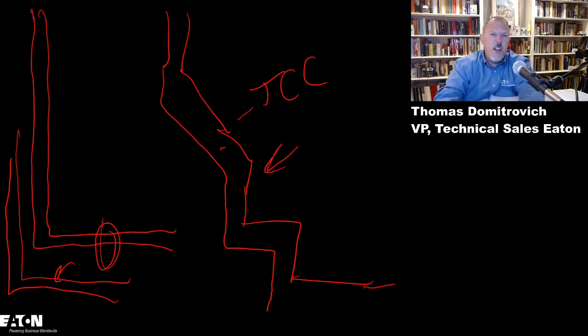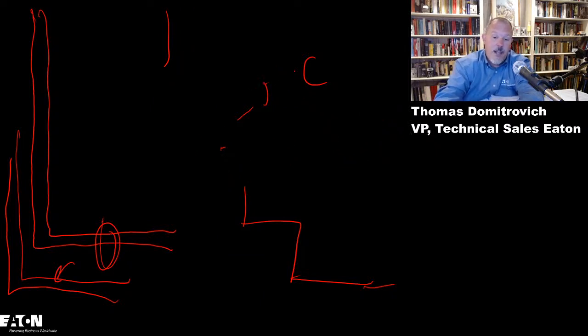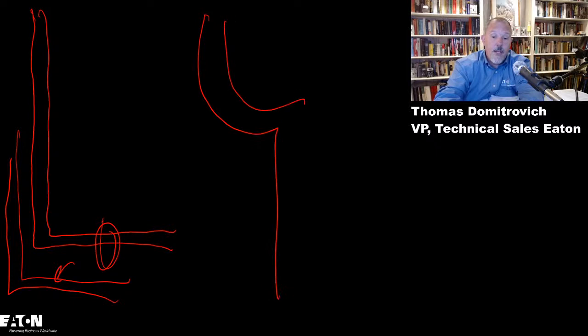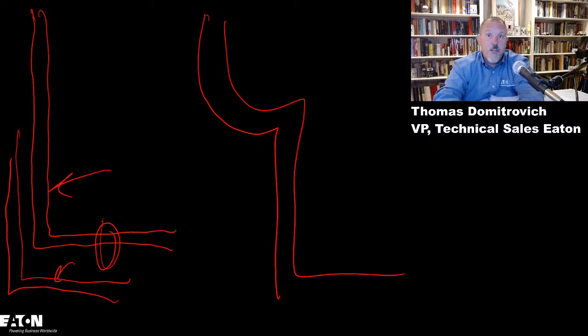This could be a good healthy F-frame circuit breaker, a larger breaker that has an electronic trip unit in it, or it could be a thermomagnetic breaker with an electronic trip unit, or a separate device that has this. So I may elect not to have the ground fault protection inside my breaker. I could have a standard thermomagnetic 200 amp breaker, and that ground fault protection of equipment is done in a relay that shunt trips that breaker and tells it when to trip.